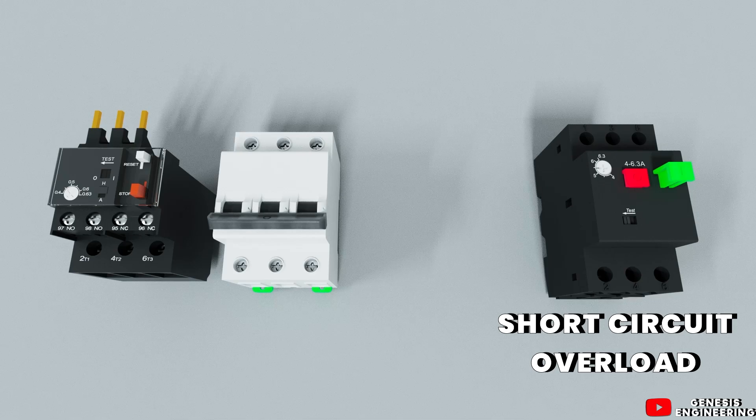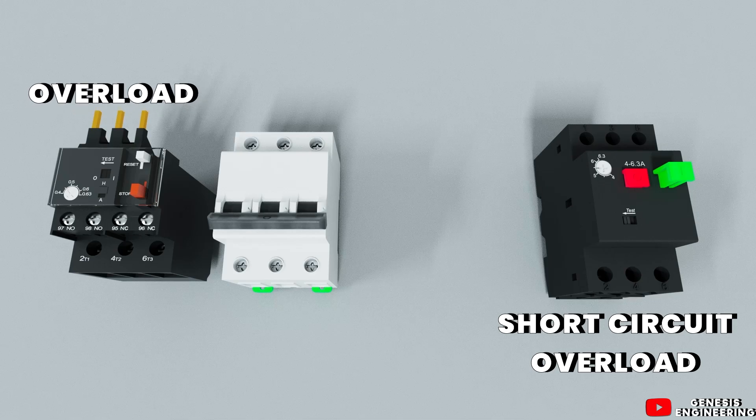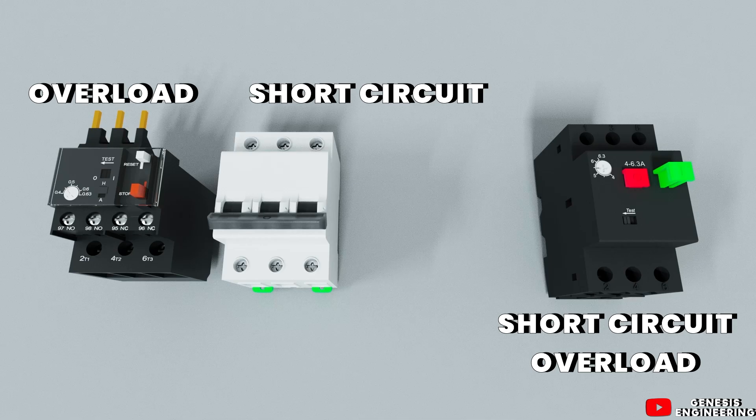The thermal relay only protects the motor against overload. So when we use the thermal relay in the circuit, it is necessary to also use a 3-pole MCB for protection against short circuit. The 3-pole MCB will protect the conductors and circuit components against short circuit.